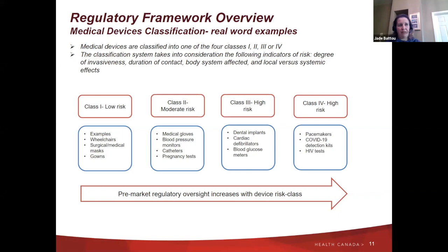What are all the classes for medical devices? Medical devices are classified into one of classes 1 to 4 by means of the classification rules set out in Schedule 1 of the medical devices regulations. Class 1 represents the lowest risk, and class 4 represents the higher risk. The risk classification of a device depends on different factors, such as the level of invasiveness, the duration of contact in the body, or the source of energy used in a device. Multiple determinants are used to classify a device as per the medical devices regulations.